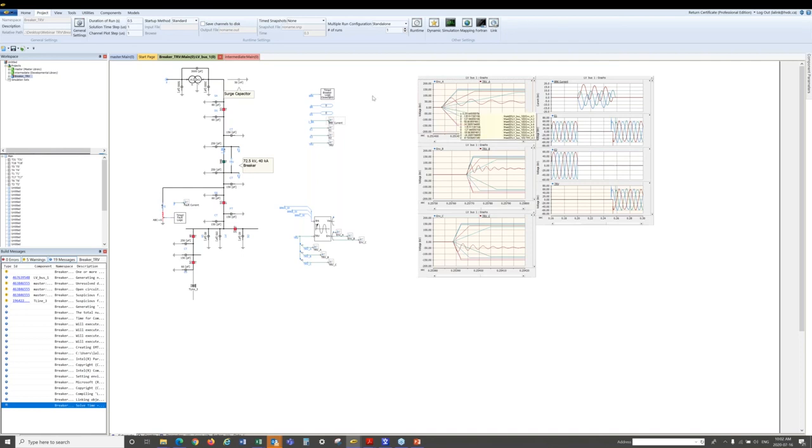As we know, this is LC sinusoidal oscillation. You know that the higher the frequency of the oscillation, the more tendency to cut the waveform. If you have a very low frequency, it goes like this, and we can get rid of this TRV violation. To get a lower frequency, as I mentioned in my presentation, the frequency is f equals 1/(2π root LC). So you can increase the C, or effective capacitance of the system, which will reduce your frequency.